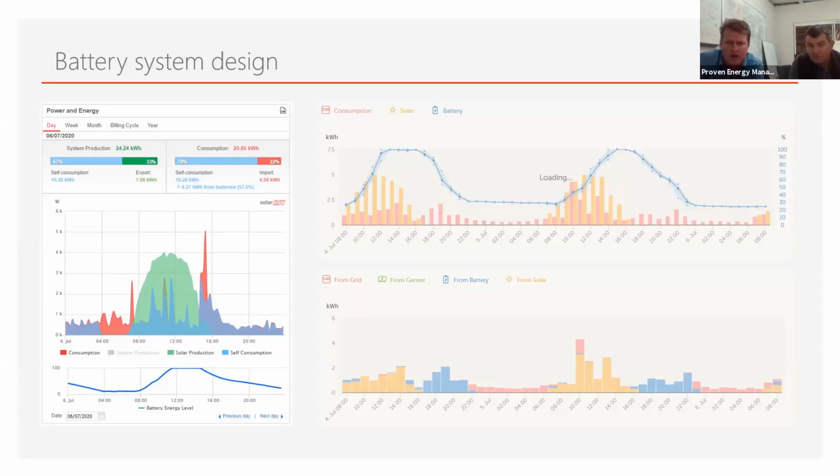Because we really end up over investing in that system where we still have an already pre-existing diesel generator system that is already working. It's reliable, but the main aim for our customer is wanting to reduce the spend on diesel fuel. And we've got to run through all those numbers. We've got to do our homework. We've got to ask a lot of questions. We've got to put monitoring equipment on that system because we can't get any information from the network. We've got to spend our time understanding what they're using now, where their headspace is in the future, right?